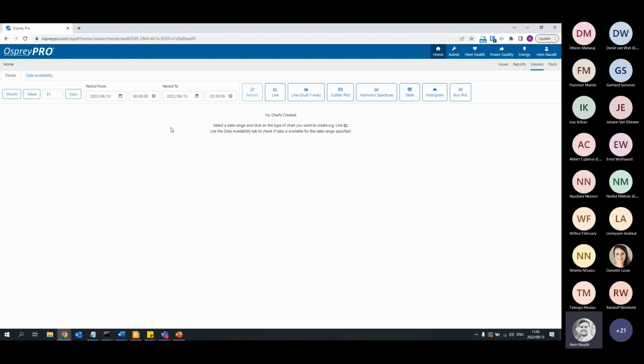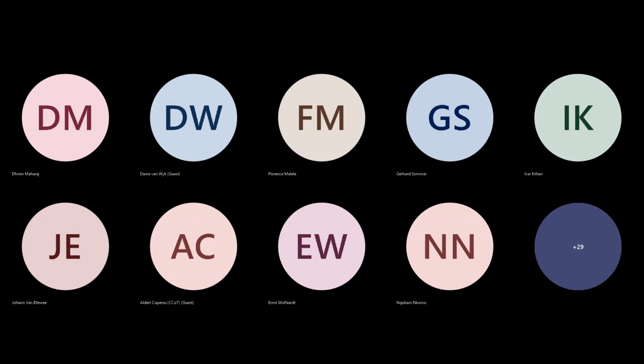So, Carl, just a very, very important thing to note here. Hein touched on it in his slides, that harmonics have phase angles as well. By looking at the prevailing phases, using a method that was developed within Eskom by Brandon, you could look at the phase angle of the specific harmonics of interest during daytime and nighttime, if there is a phase shift attributable.